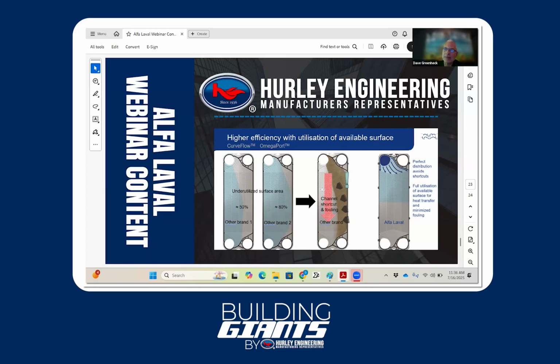By the way, a quick note. It's always good to have ports so you can check temperatures and pressures so you can see the performance over time against your submittal. That's a great indication of when you are scaling up. And it's great when you open for a cleaning to take pictures and say, okay, this has been a year and a half since we bought this. This is what it looks like. Then they're like, well, that's a lot of scale. We'll open it in a year and keep doing that picture and timing so you can fine tune your maintenance cycle. Yeah, for our service contractors out there too.